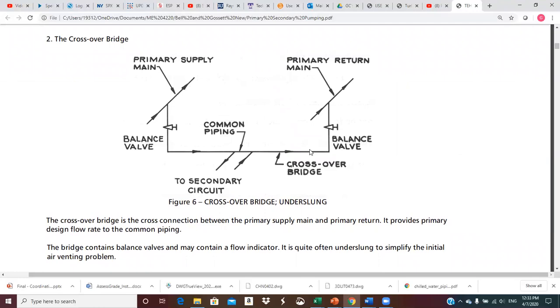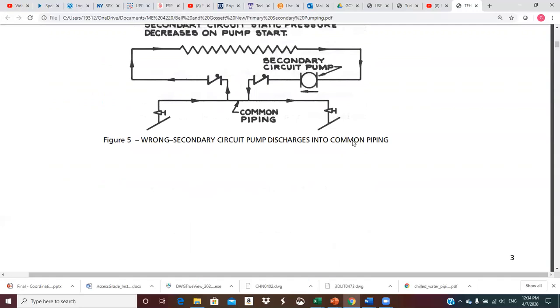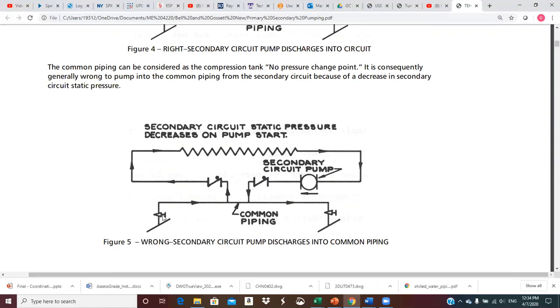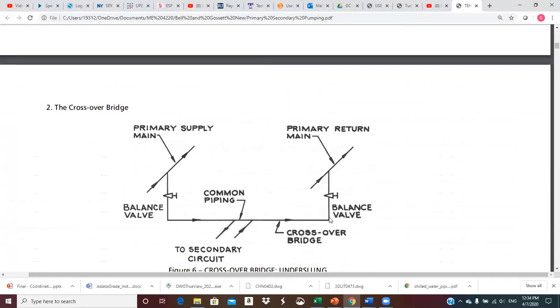The crossover bridge is the cross-connection between the primary supply main and the primary return. It provides the primary design flow rate to the common piping. The bridge contains balancing valves and may contain a flow indicator or flow meter. It is quite often underslung to simplify initial air venting — underslung means below the mains. If it comes vertically upward it's an overhead crossover; if it hangs below it's an underslung crossover.